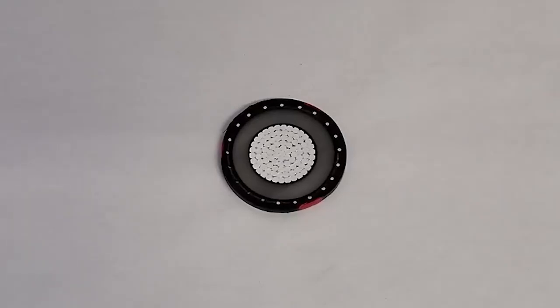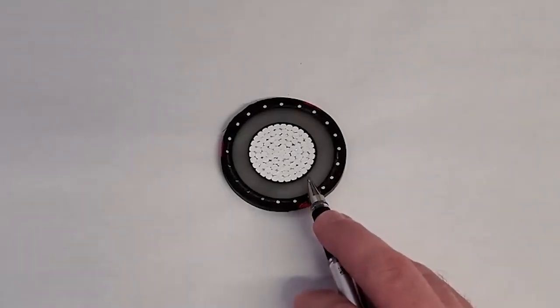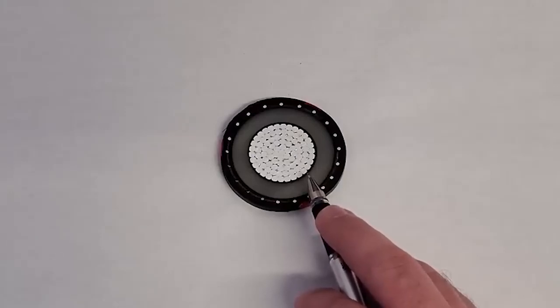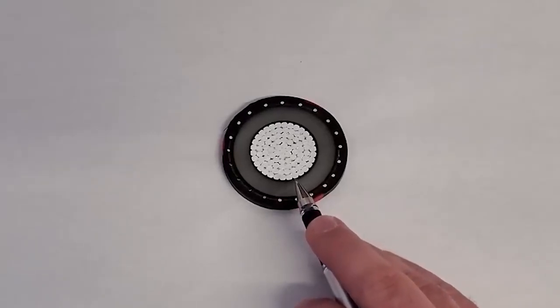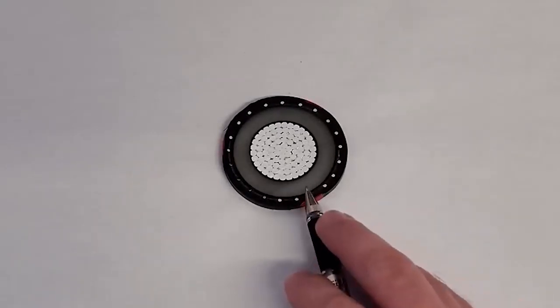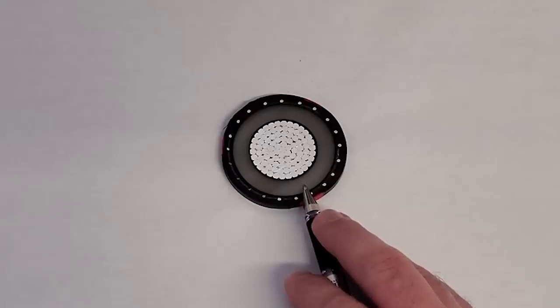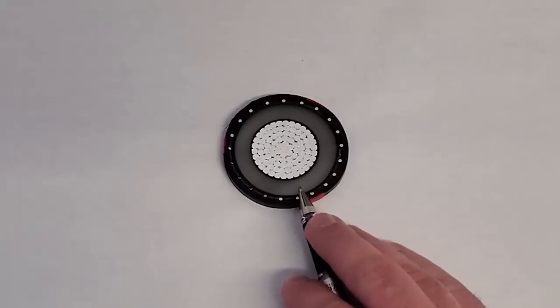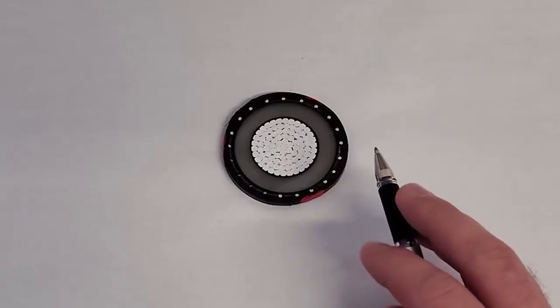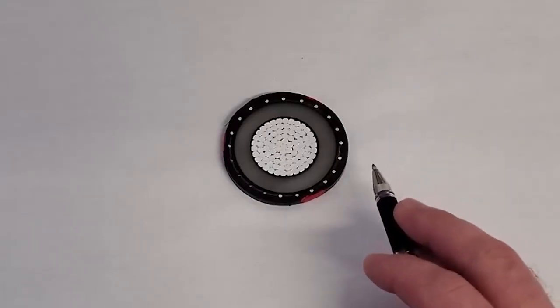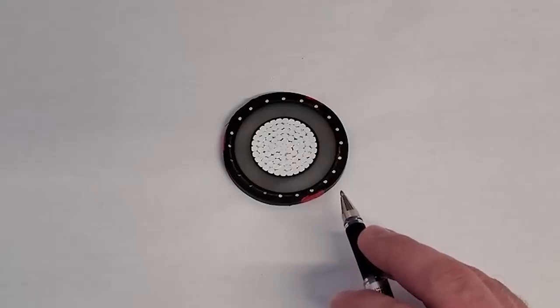So overall, the XLPE is a great insulation, and it's mainly used on the wind farms. And this is 345 mils, which is 345 thousandths thickness. There are a lot of IEEE tables and different tables that will tell you what the insulation thickness is supposed to be. You can actually buy cable with a higher insulation rating than you need to. This is a 100% insulation, which means that's what you need to operate this cable safely. You can also purchase 133% and 166%. A lot of people like that extra fluff in there.